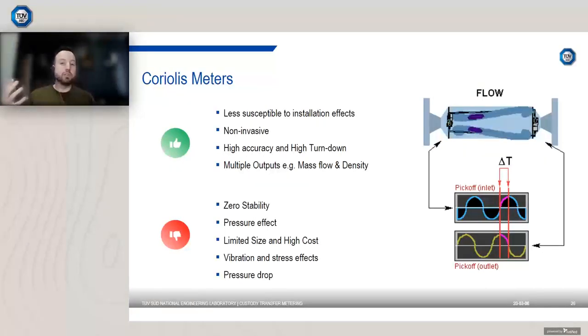In terms of the size of Coriolis meters, they tend to be limited compared to other technologies. So, typically 10, 12 inch is the maximum size. You do get up to sort of 16-inch flanges now, but as you go up in size with Coriolis meters, the costs do increase significantly. Another disadvantage is they'll introduce a pressure drop in the line. Now, depending on the flow rate, that can be quite significant. So Coriolis meters typically will have higher capital costs up front than some of the other technologies, but again, they've got numerous advantages, so you need to balance that out. In the long run, they might actually work out more cost effective than one of the more traditional flow measurement technologies.